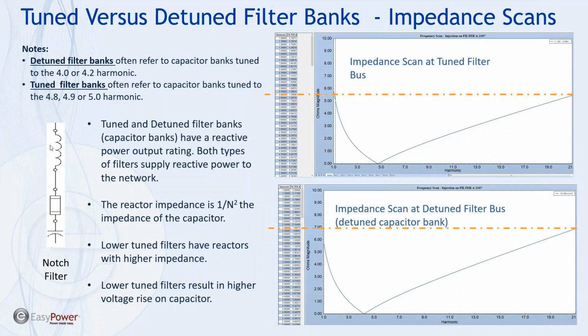To the left here, I show the diagram for a notch harmonic filter or tuned filter. If it's tuned to 4.7, again, we're calling that a tuned filter. The reactor and capacitor have a frequency tuning point of 4.7, 4.8, 4.9, right? And a detuned filter would be 4.0 to 4.2. So the objective here of tuned filters and detuned filters normally is to supply reactive power. That's the first thing. And they both do that. The only difference is the choice of reactor impedance. And basically, we take XFC and we multiply by 1 over n squared, where n is the desired tuning point. So if you study the equation just a little bit, you will see that lower tuned filters have a higher reactive impedance, and higher tuned filters have a lower impedance.